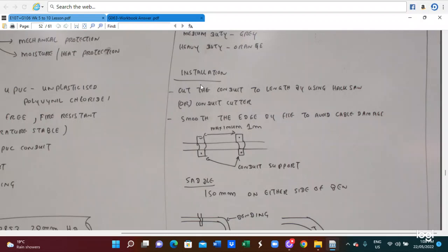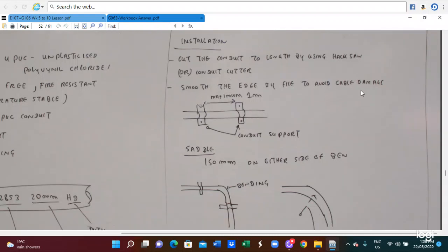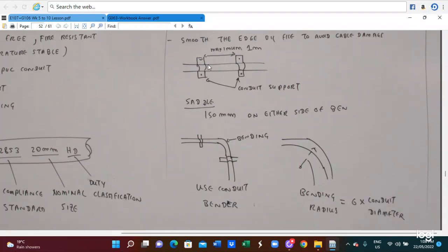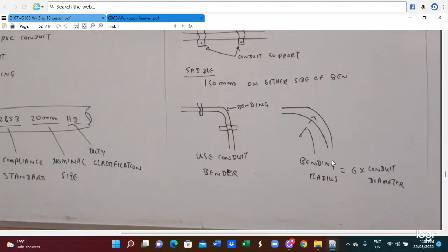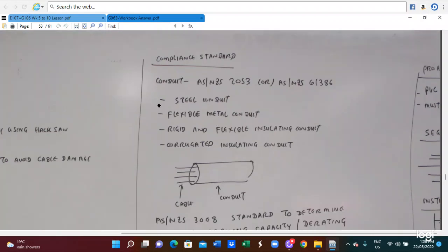Installation method is that we have to cut the conduit. Tools are a hacksaw and a conduit cutter, and smooth the edge by using a file to avoid damage, and we have to use a saddle and also the bending system. So bending is when you bend it, there will be a radius of six times the conduit diameter.